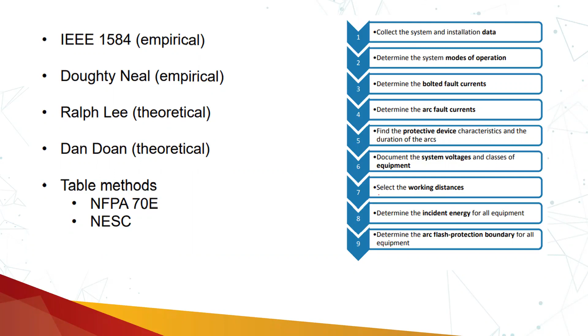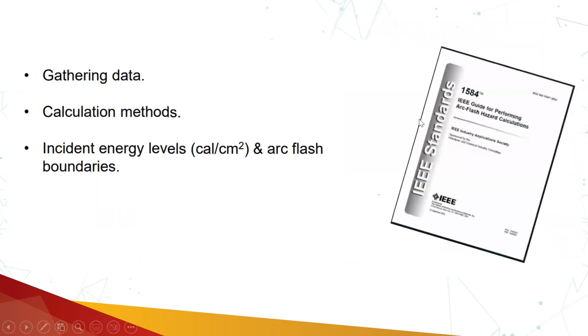So basically this method, the IEEE 1584 method, can be used to calculate the incident energy, the arc flash boundary, and what could be the suitable working distance for working at that particular location. So this is how IEEE 1584, which is basically the guideline for performing arc flash hazard calculations, is being used. And Annex D talks about this standard for calculation of the incident energy.